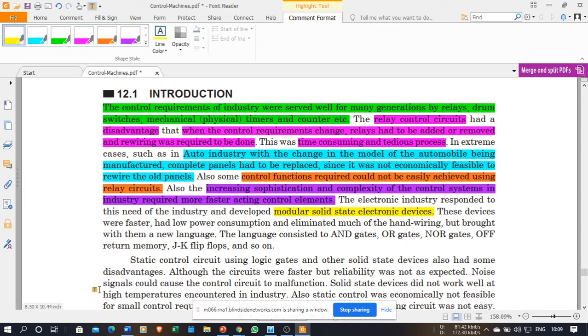When using a relay, I need to energize the coil, then a magnetic field will establish, and switching action will take place from the NO contact to the NC contact. This takes time in milliseconds, up to about 10 milliseconds. But in case of solid state devices like transistors or IGBTs, which we study in power electronics, the switching time is in microseconds, sometimes even nanoseconds. So these devices are faster. Advantages of these devices are that they are faster, have low power consumption, and eliminate much of the hand wiring. The rate of operation of these devices is very high compared to relay based circuits.